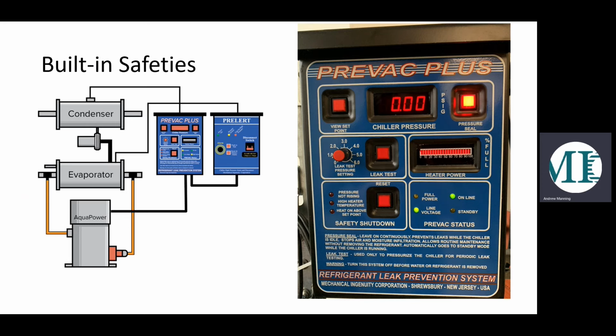The second safety shutdown is the high heater temperature. This is going to shut down the PREVAC if the heaters are getting too hot and you're at risk of overpressurization. So we control the water temperature with two sensors inside the boiler. One is a thermistor that limits the water temperature to 90 degrees Fahrenheit, and the other is a temperature switch that shuts down at 105 Fahrenheit. And the final safety shutdown notification light you might see is heaters on above set point. So if the power is going to the heaters above our set point, we shut down the PREVAC. And the reason for this is because the triac failure mode is a closed circuit.